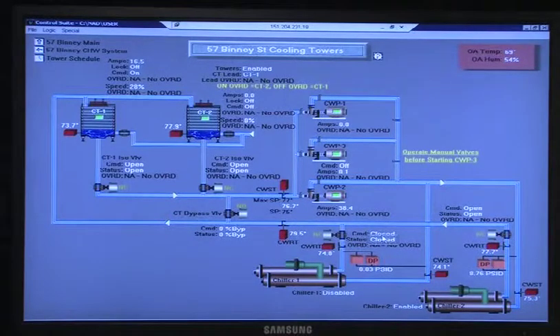What is this here? Command closed, command status closed. Oh, this one's for this. There it is. I just lost this. This commanding is for that valve. So because this is enabled, that's commanding this valve to be open to flow water. The chiller controls the valve. The command. All right. And then it discharges out of it.